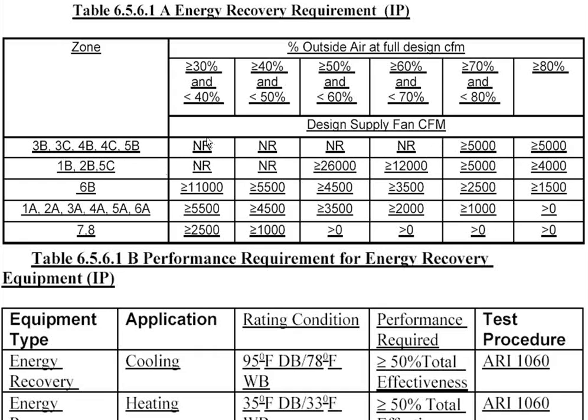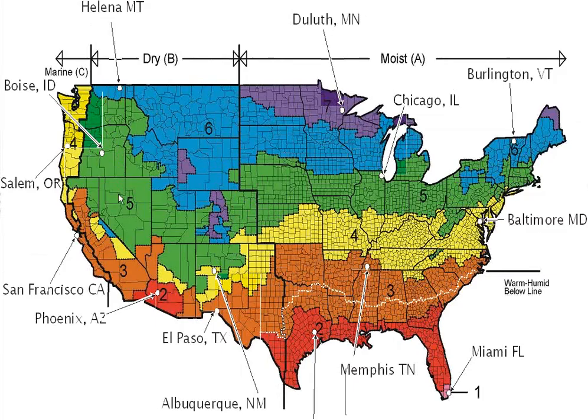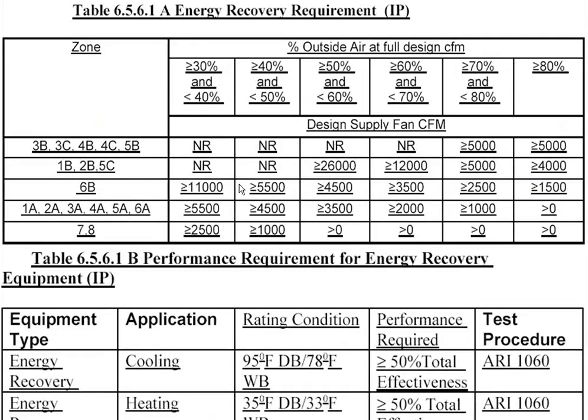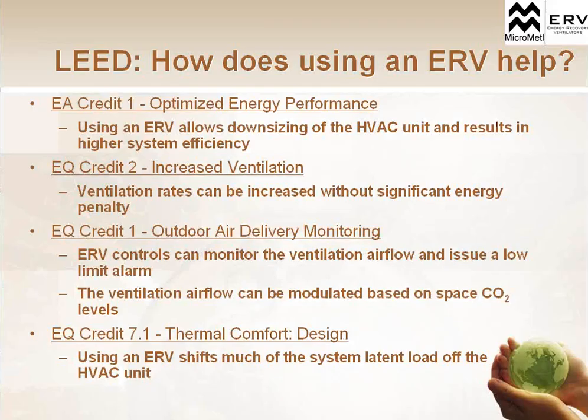If you look at the next, 1B and 2B, down in that dry climate area in the Texas, New Mexico area, only when you get up to large CFM ranges, 26,000 CFMs, and half of that is outside air, are they starting to require ERVs. So they've kind of broken it down and gotten more specific on when an ERV is really going to provide those energy savings. And we said the part 2 to that requirement is that they have to have 50% total effectiveness. And I'll break down what that total effectiveness actually means in a few slides here.